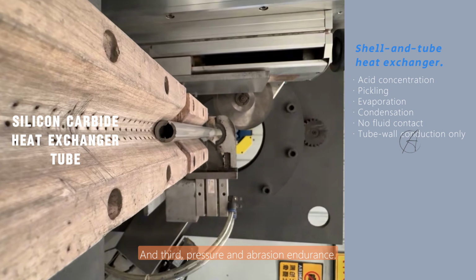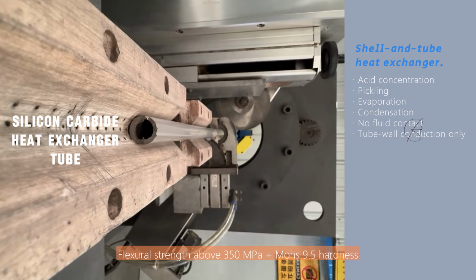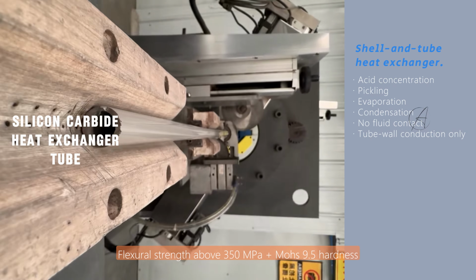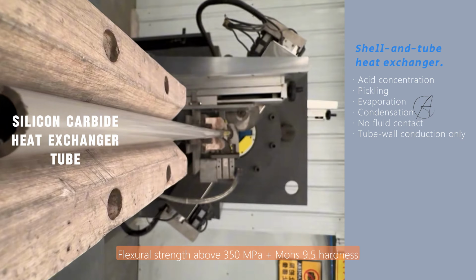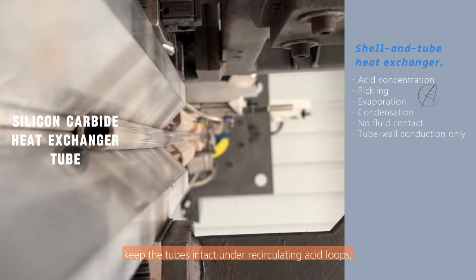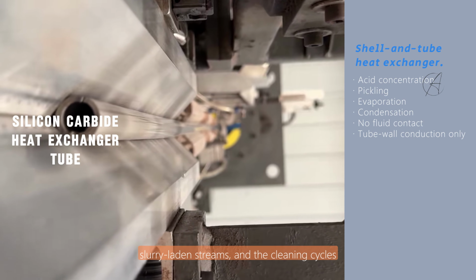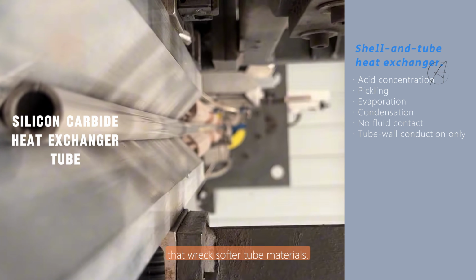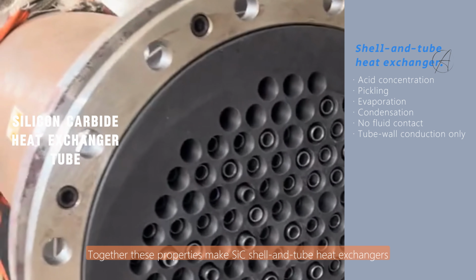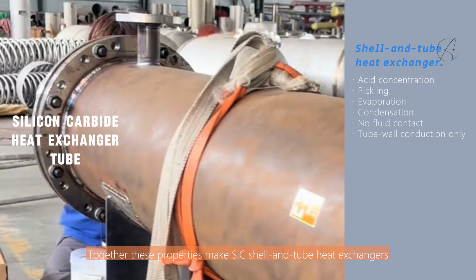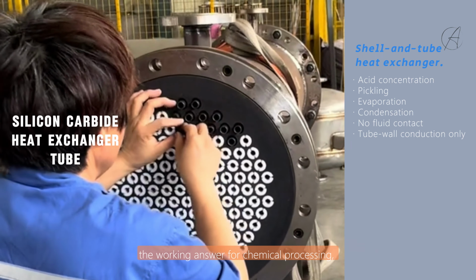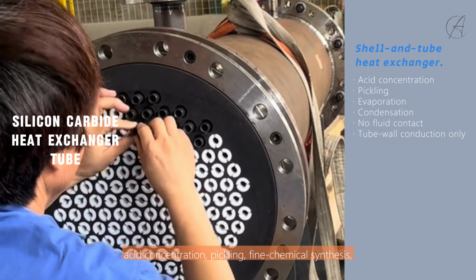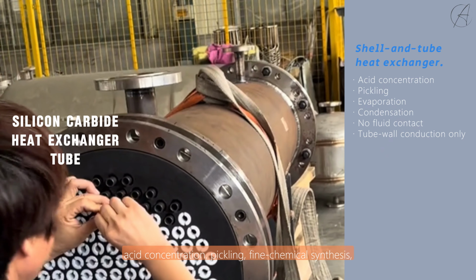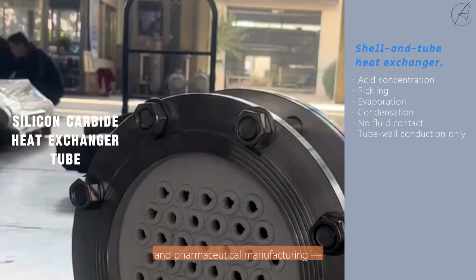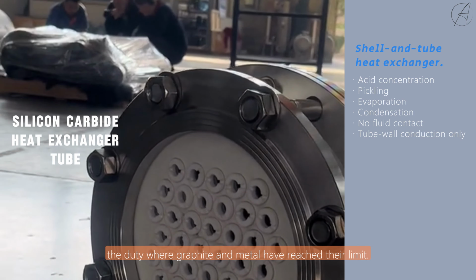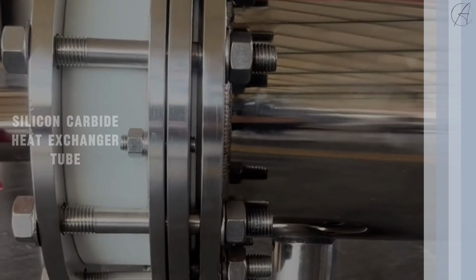And third, pressure and abrasion endurance. Flexural strength above 350 megapascals plus Mohs 9.5 hardness keep the tubes intact under recirculating acid loops, slurry-laden streams, and the cleaning cycles that wreck softer tube materials. Together, these properties make silicon carbide shell and tube heat exchangers the working answer for chemical processing, acid concentration, pickling, fine chemical synthesis, and pharmaceutical manufacturing, the duty where graphite and metal have reached their limit.